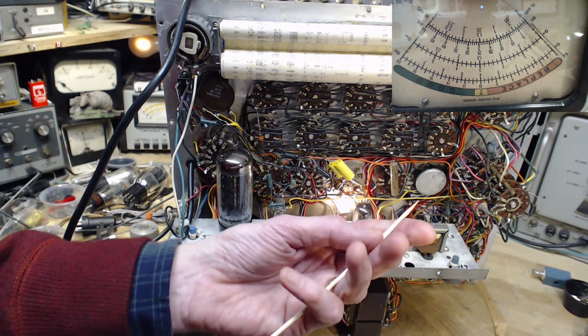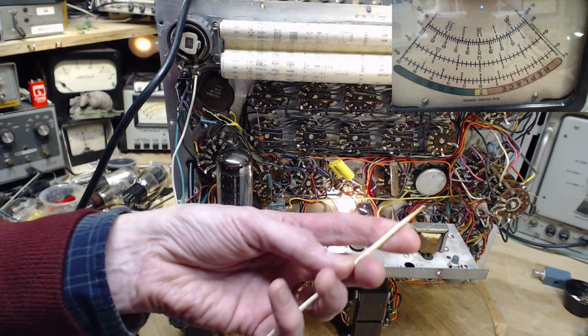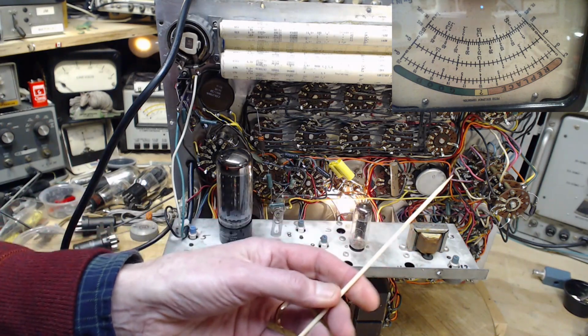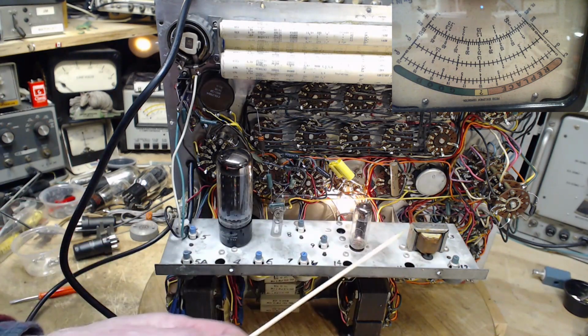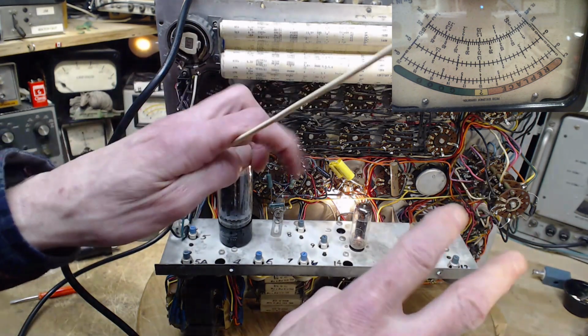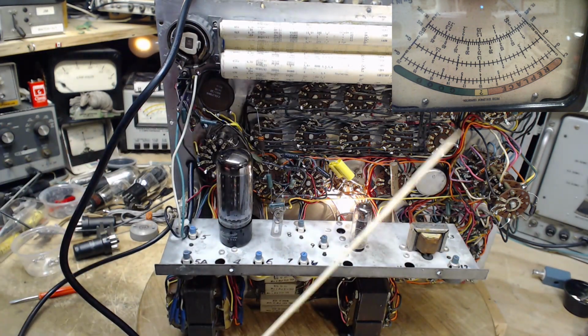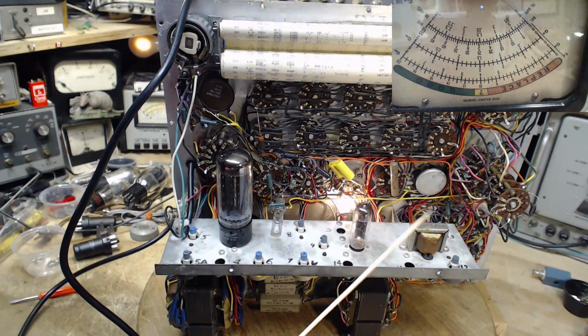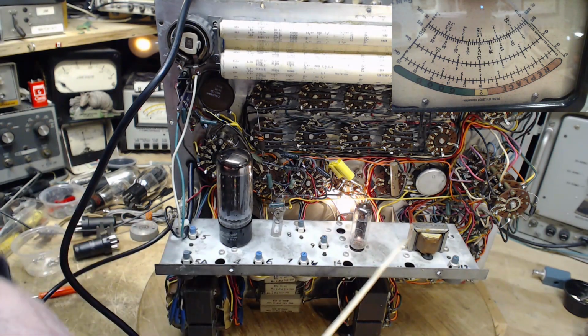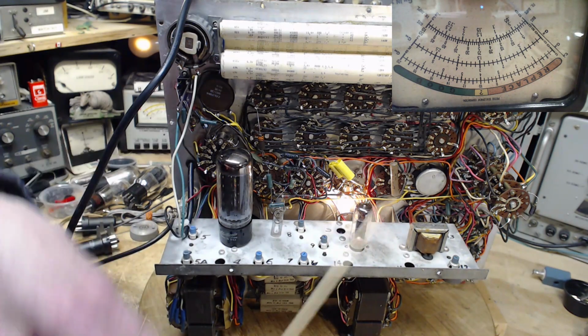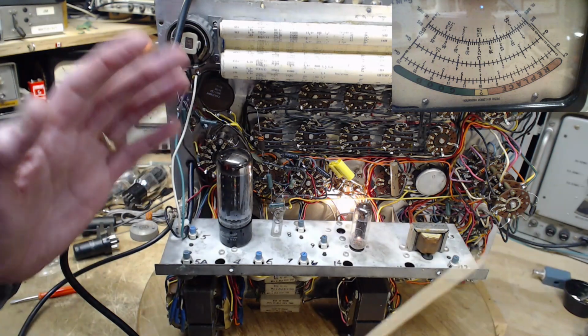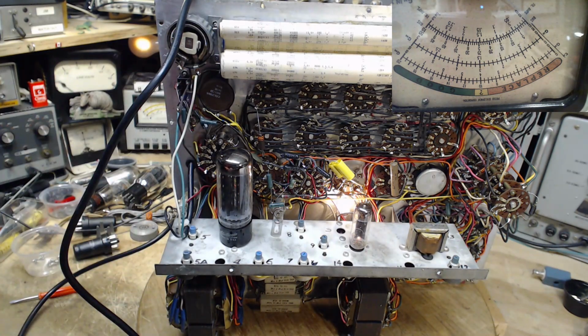So the industry, or somebody somewhere, built some of these new extruded cables and put them through life testing, and determined that this cable would probably operate safely without failure for 1,000 years. That was an actual determination done from the study. How do you do life testing? You beat the cable up, you make it hot, you stomp on it, do whatever you like to try to imitate age or time going by.